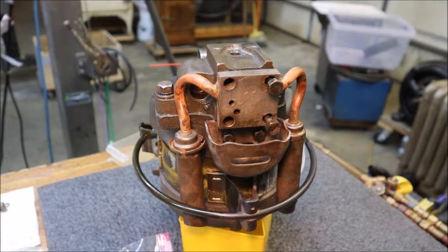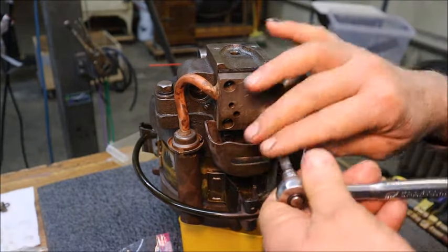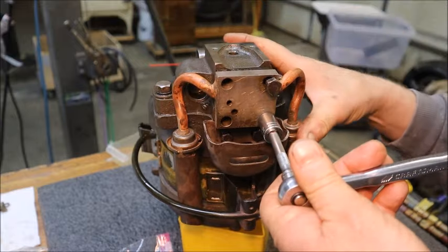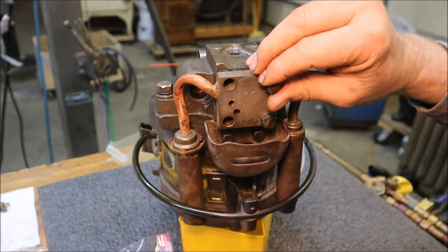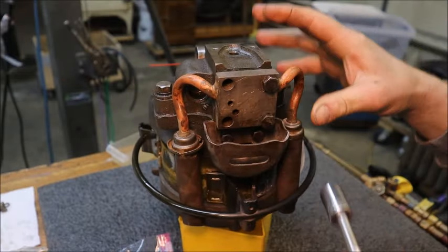When those bolts are tightened it's going to have to sort of form that copper tube down there. Apparently when I was tearing this down I bent it a little bit because I was just trying to get it apart - at that point I didn't know whether or not I was going to attempt to overhaul it, so I was potentially not as gentle as I should have been. I start out every project with the hope that it will be fixable, and until I see something that I know 100 percent is not restorable, I operate under that assumption.